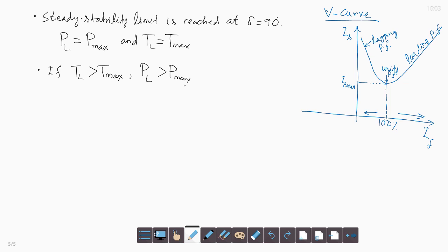Otherwise large current will set in, because there will be no induction, because there are different speeds. So, the current will be very large, which can damage the machine. So, when the machine comes out of synchronism, loses synchronism, immediately circuit breakers must disconnect the machine. This is very important for medium and large power motors.